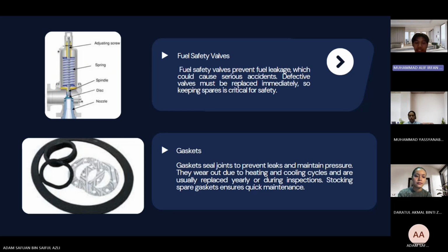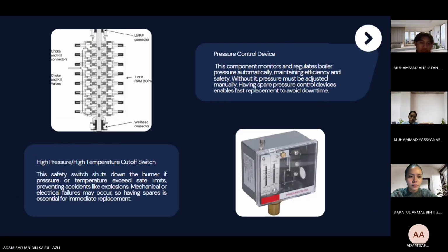Next, gasket. Gaskets seal joints to prevent leaks and maintain pressure. They can wear out due to heating and cooling cycles and are usually replaced yearly or during inspection. Stocking a spare gasket ensures quick maintenance. High pressure, high temperature cutoff. This safety switch shuts down the burner if pressure or temperature exceeds safe limits. It prevents accidents like explosion. Mechanical or electrical failure may occur, so having a spare is essential for immediate replacement.